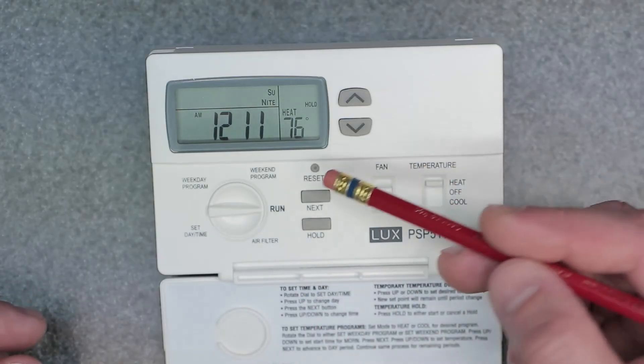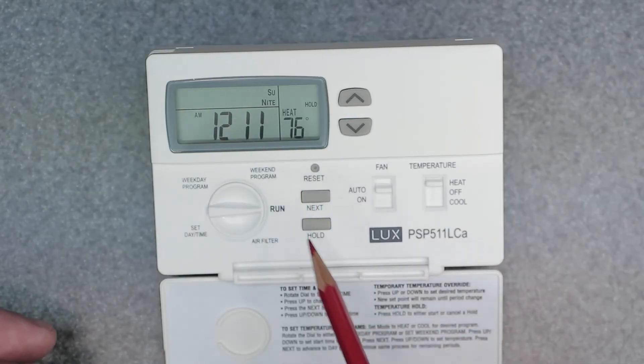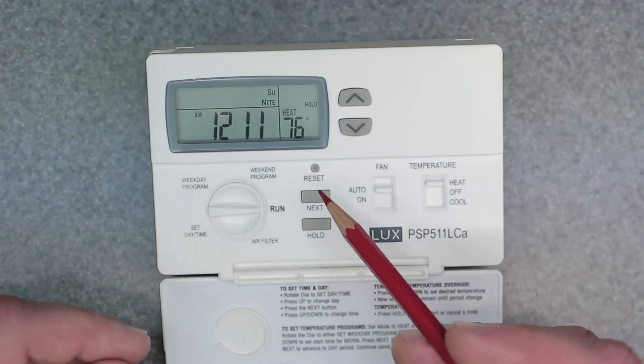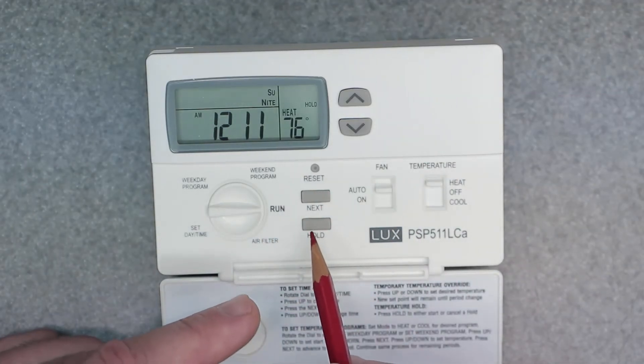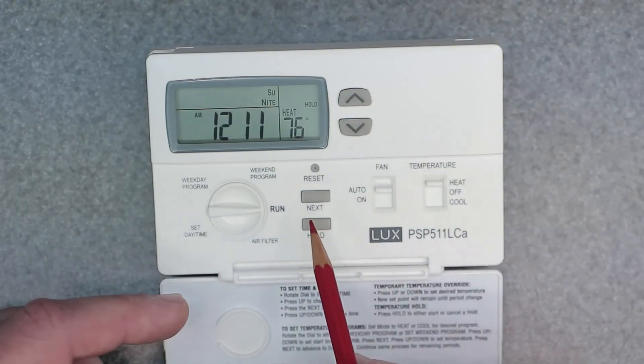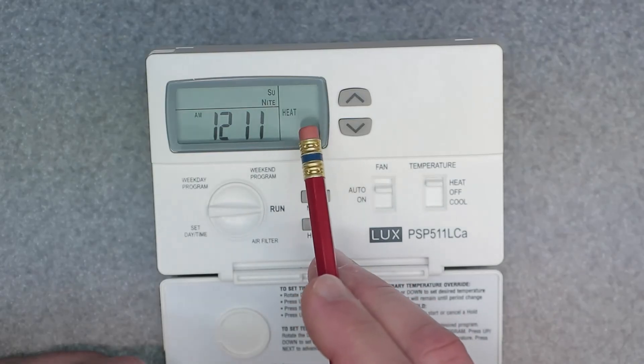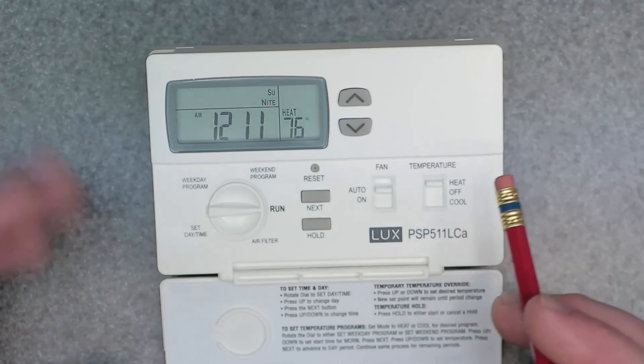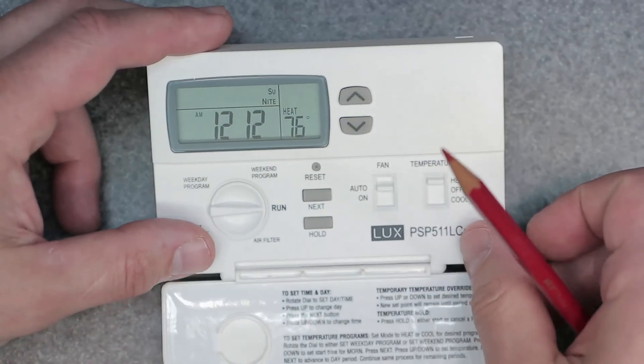Also, if you do a software reset using this button right here, it's going to change that. There's also a hardware reset on the back — I'll talk about that in another video — but there's a difference between the two resets. Once you hit hold, you're holding that set point temperature of 76 degrees. To cancel it, just hit hold one more time. As you can see, 'hold' disappeared from the screen and now you're back to your regular program schedule set points however they are programmed in the device.